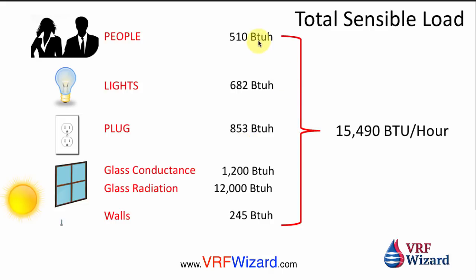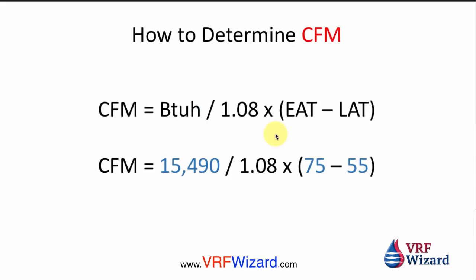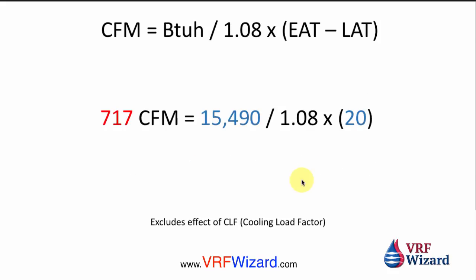Adding all those sensible loads together — people load, lighting load, plug load, glass conductance, glass radiation, and wall conductance — gives a total of 15,490 BTUs per hour sensible. To determine the CFM, plug the values into the sensible heat equation: we know the room design temperature, we know the supply air temperature, so we solve for CFM. The result is 717 CFM required for that room based on that load.